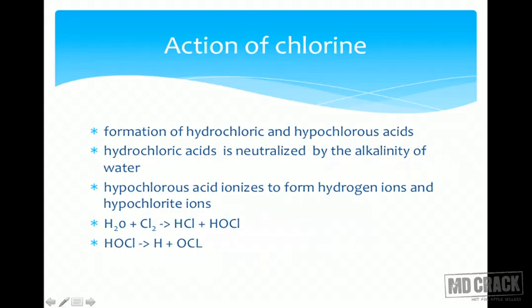Action of chlorine: chlorine forms hydrochloric acid (HCl) and hypochlorous acid (HOCl). Hydrochloric acid neutralizes the alkalinity of the water — this is important because chlorine does not work if the water is alkaline; the pH of the water must be close to 7. So the HCl that forms reduces the alkalinity and thus itself helps in chlorination.